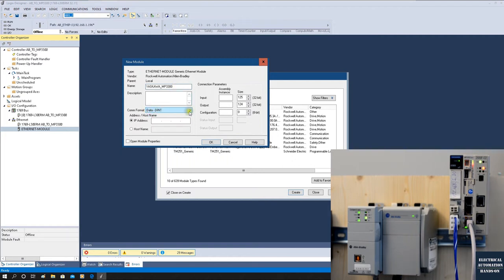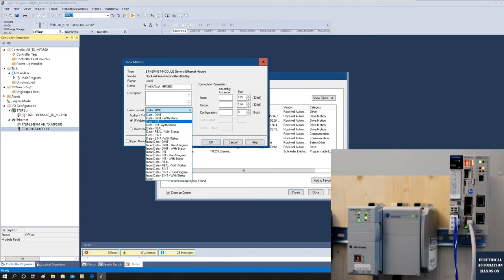Name the module 'Yaskawa_MP3300'. Then select the data format — we can pick Integer. In some cases you might define four bytes as a unit when transferring position or velocity data, but since I created two WORDs on the Yaskawa side, I'll configure Integer format. Set the IP address to 192.168.1.10 — this is the MP3300 motion controller's IP address. Selecting Integer changes the unit size to 16 bits, which is two bytes per unit. Now recall the assembly numbers from the Yaskawa hardware configuration.